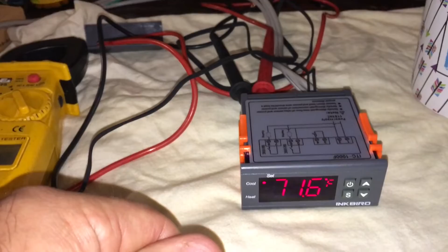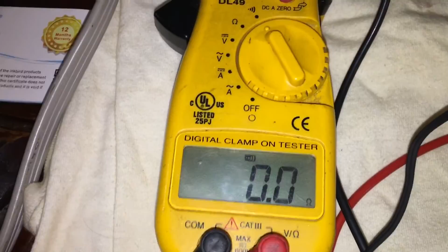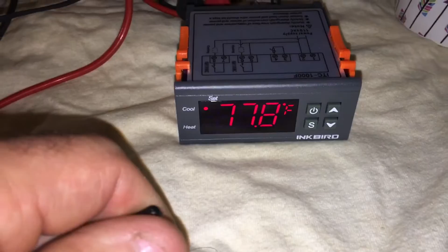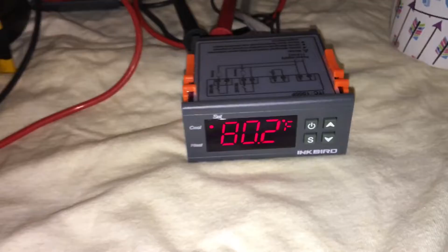So I have this set for 60 degrees and 10 degree differential, so at 70 degrees, there we go. At 70 degrees, she tones out. That's a tone. That means the set of contacts closed. So they closed at 70 degrees. It's in cooling mode. Okay, it's 80 degrees between my fingers right here. So now I'm going to stick it back in here.